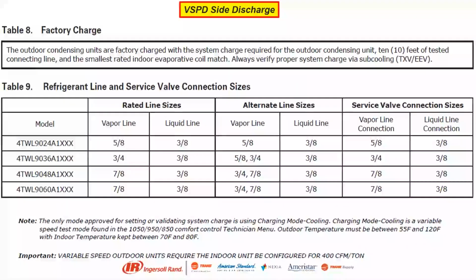I like to touch on the line set sizes because there is no 1 1/8 by 3/8. So be aware, we can run a 3/4 for a 5-ton variable speed side discharge. See, this is all in the installation manual or on your comfortsite.com or ASDealerNet.